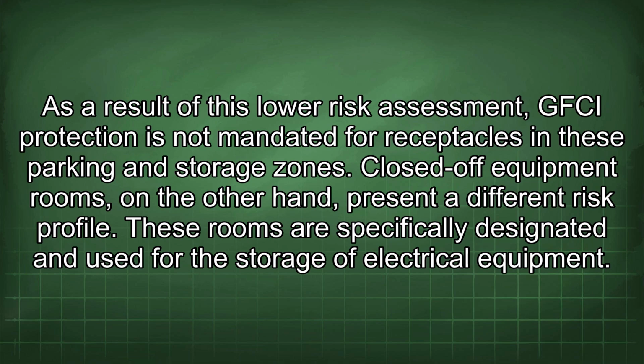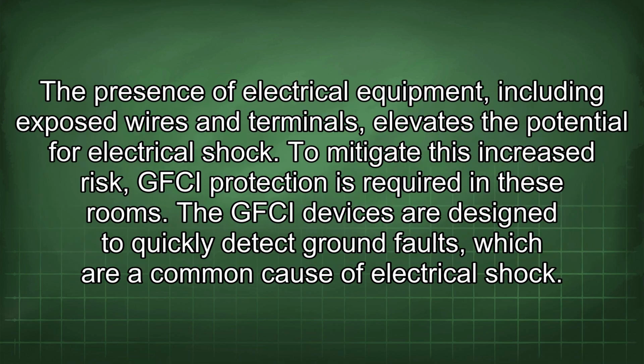and storage zones. Closed-off equipment rooms, on the other hand, present a different risk profile. These rooms are specifically designated and used for the storage of electrical equipment. The presence of electrical equipment, including exposed wires and terminals, elevates the potential for electrical shock. To mitigate this increased risk, GFCI protection is required in these rooms.